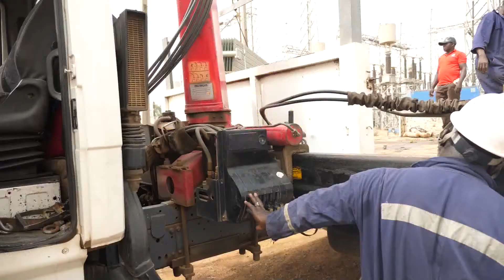If you look at the switch yard, before there were two by 60 MVA. So already the other 1 by 60 MVA on my left is still in circuit, while the new one, which is replacing the faulty one, is back. As soon as it is installed, commissioned, and energized, the load that was being suppressed from the former faulty transformer will be restored.